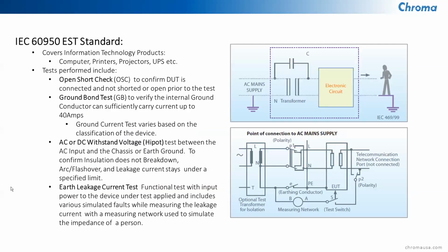So IEC 60950 standard has some requirements for open and short testing. This is not a mandatory requirement. We include it in all of our test equipment. And what this is for is to confirm that the test equipment is properly attached to the device under test. And with this, you can ensure that when you perform the test, that it is being performed properly, that you won't get any false pass due to the fact that it may be open circuit.